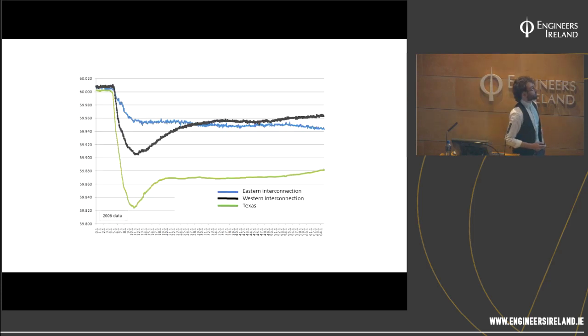So that's from a system perspective. Okay, so now I'm saying the frequency falls at a greater rate. Why do I care about that? Well, like any set of machines, power plants are built for an optimal speed and optimal operation. So there's consequences for having extreme frequency excursions, and that's why the system operator wants to have inertia on the system, because it will guard against you getting into those extreme territories.